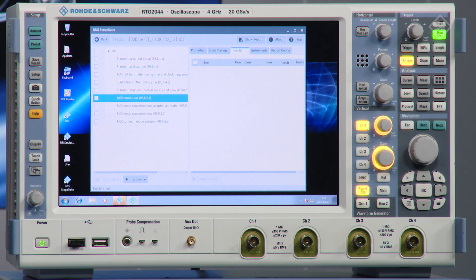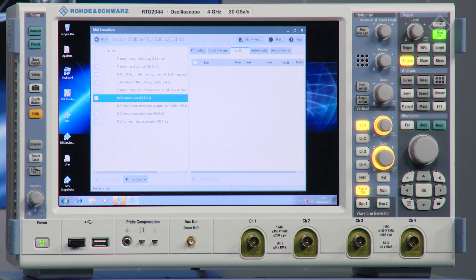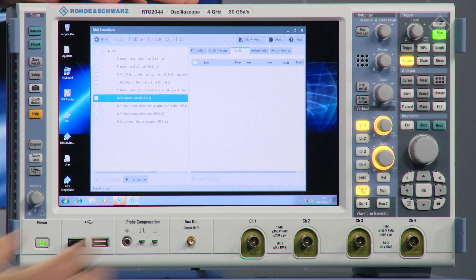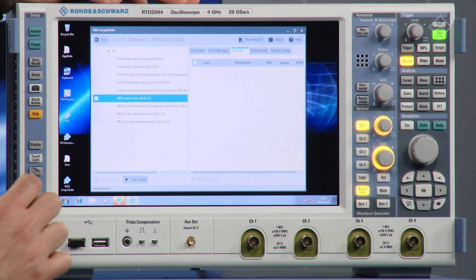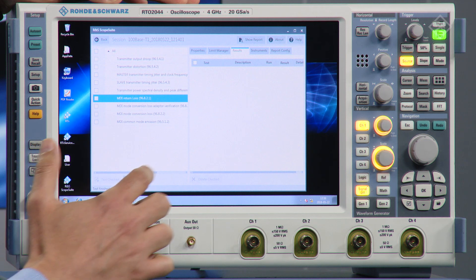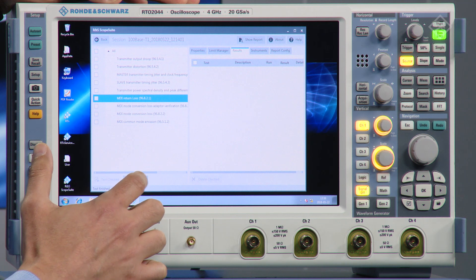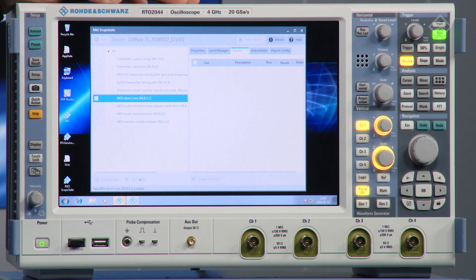For the RTO we use the scope suite, which is an automation software that helps to control the oscilloscope. What we need to do is run up the scope suite and choose the MDI return loss to make this testing.